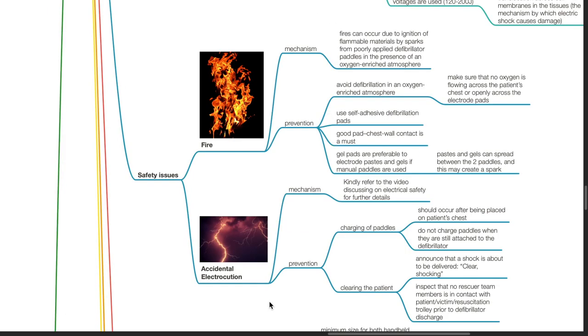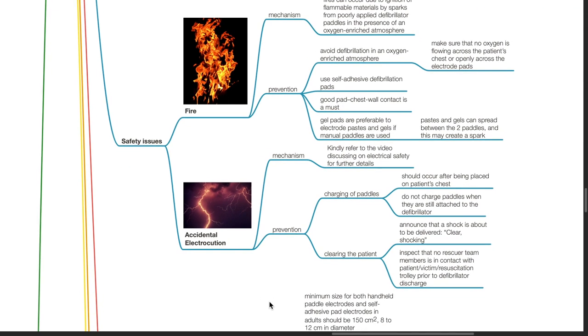Safety issues of defibrillation include fire and accidental electrocution. Fires can occur due to ignition of flammable materials by sparks from poorly applied defibrillator paddles in an oxygen-rich atmosphere. Prevention: avoid defibrillation in an oxygen-rich atmosphere; ensure no oxygen is flowing across the patient's chest or electrode pads; use self-adhesive defibrillation pads with good pad-chest wall contact; gel pads are preferred to electrode paste and gels if manual paddles are used, as paste and gels can spread between the two paddles and create a spark.